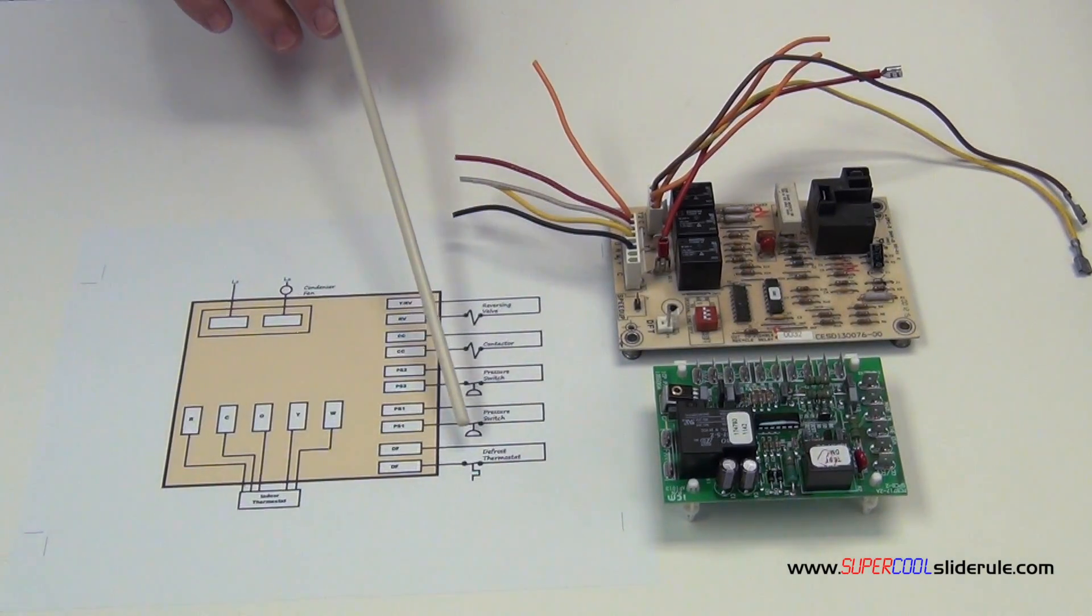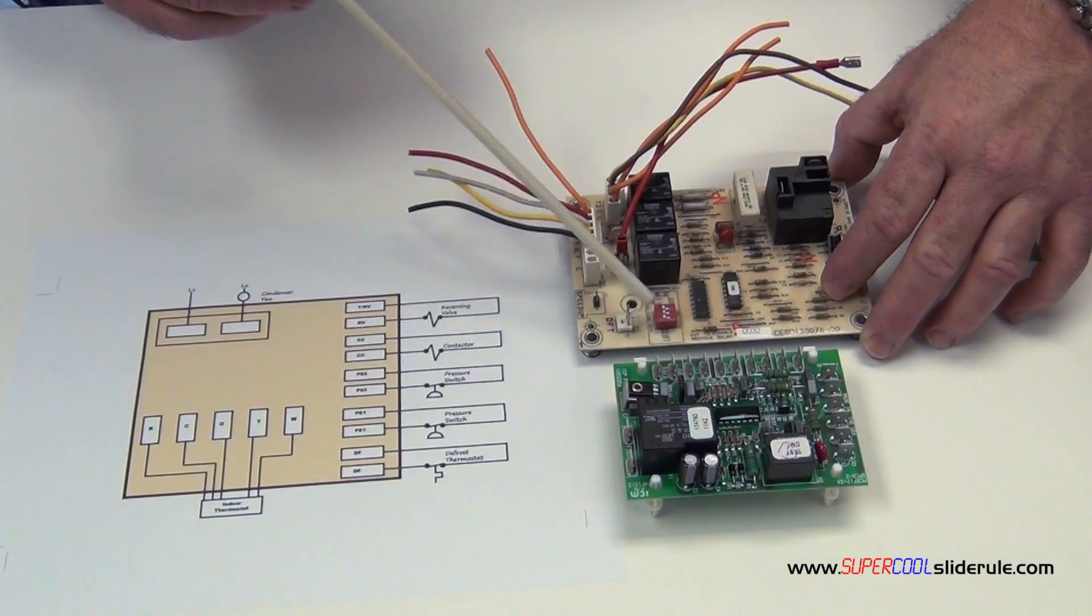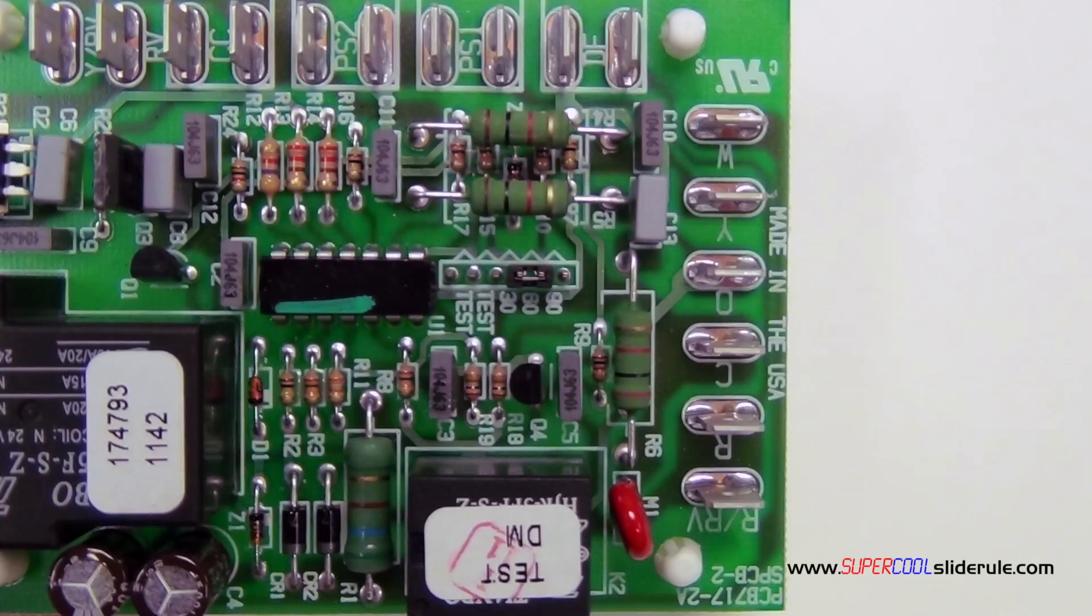That time is important because every one of these boards will have defrost settings. This one has dip switches that you set to control how long it runs before it goes into defrost, and this one here uses a jumper right there that you can manually change the time that it runs before it defrosts.